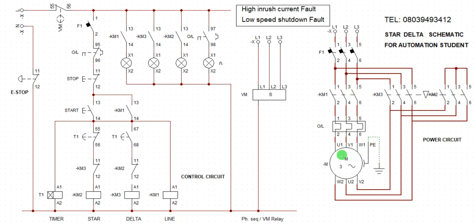The motor is supposed to receive power through two paths when working on delta, and through one end with the star bridging when working on star. If the star end is not bridged, the delta power shouldn't come through. If the star contactor is not closed, power shouldn't pass through to the motor. To rectify this issue, we need to create an auxiliary branch in the control circuit.